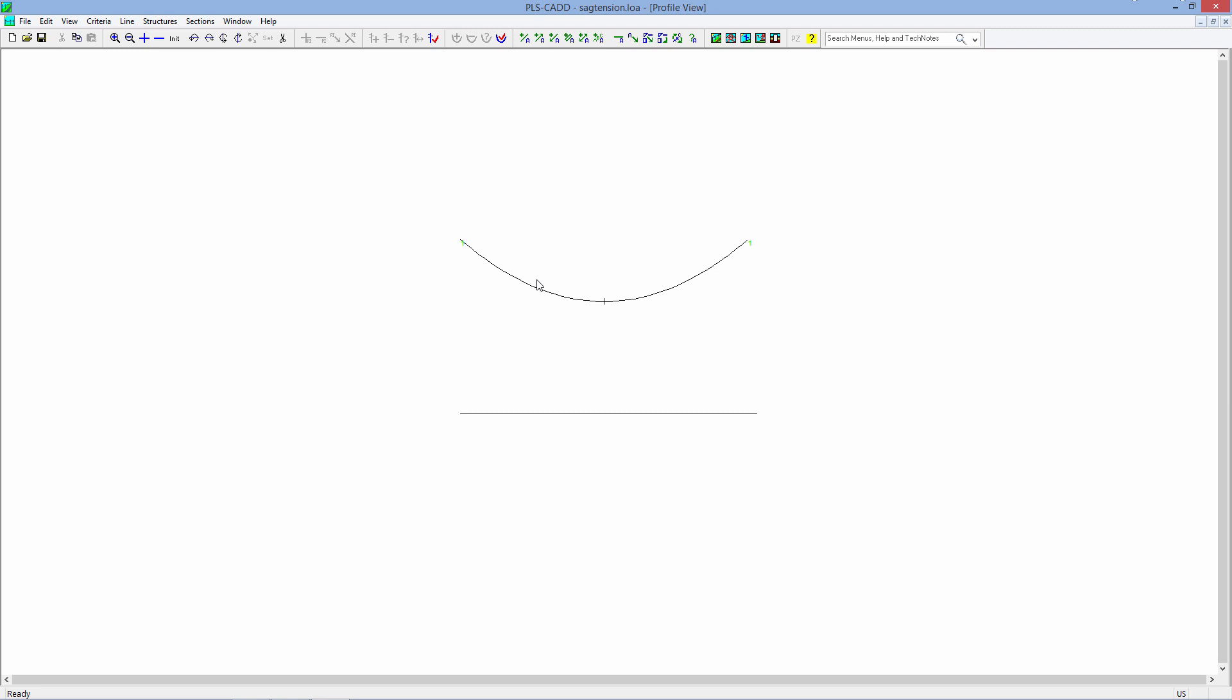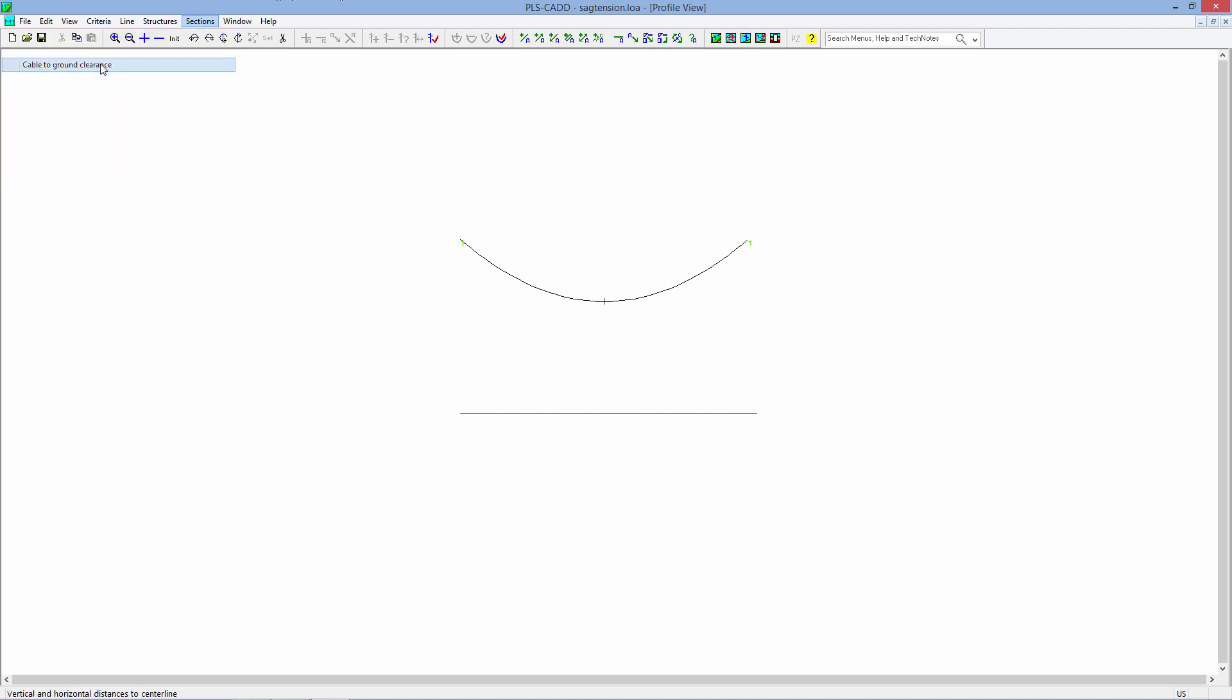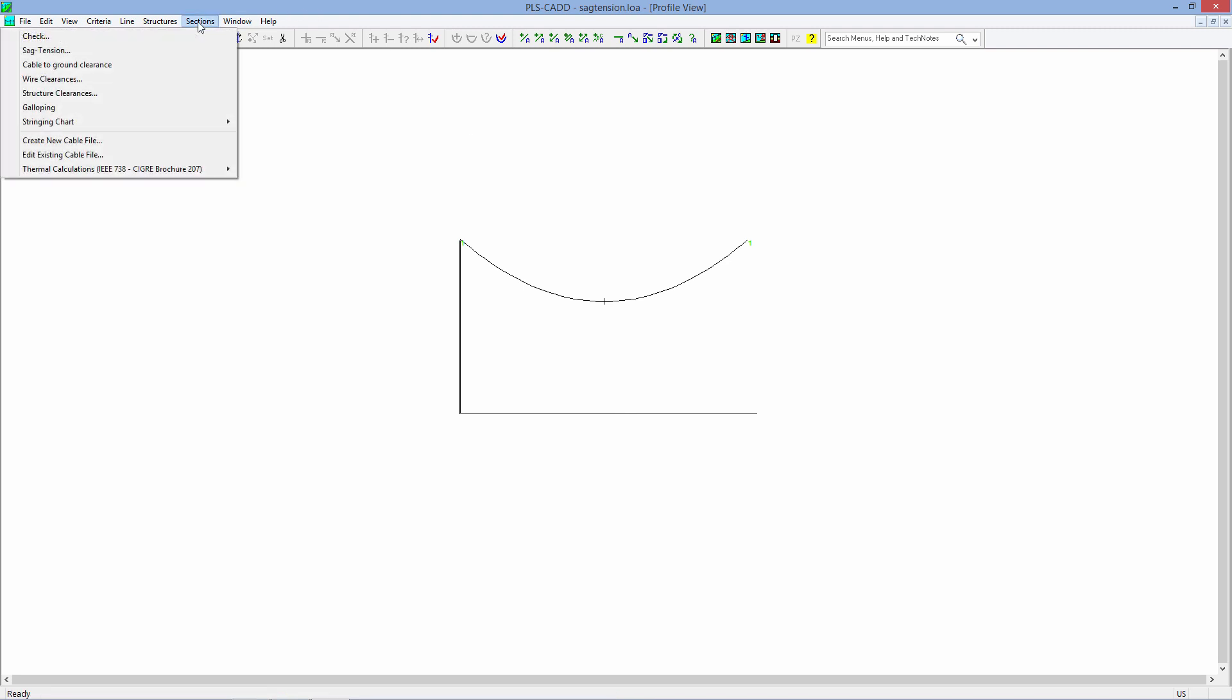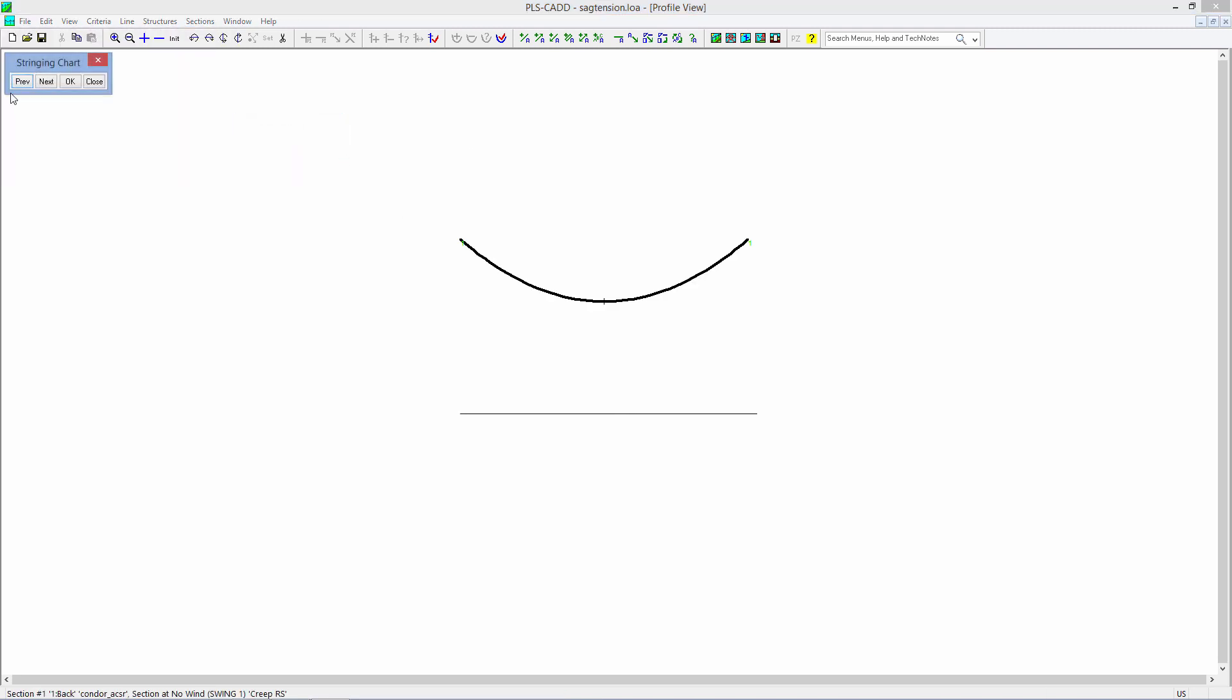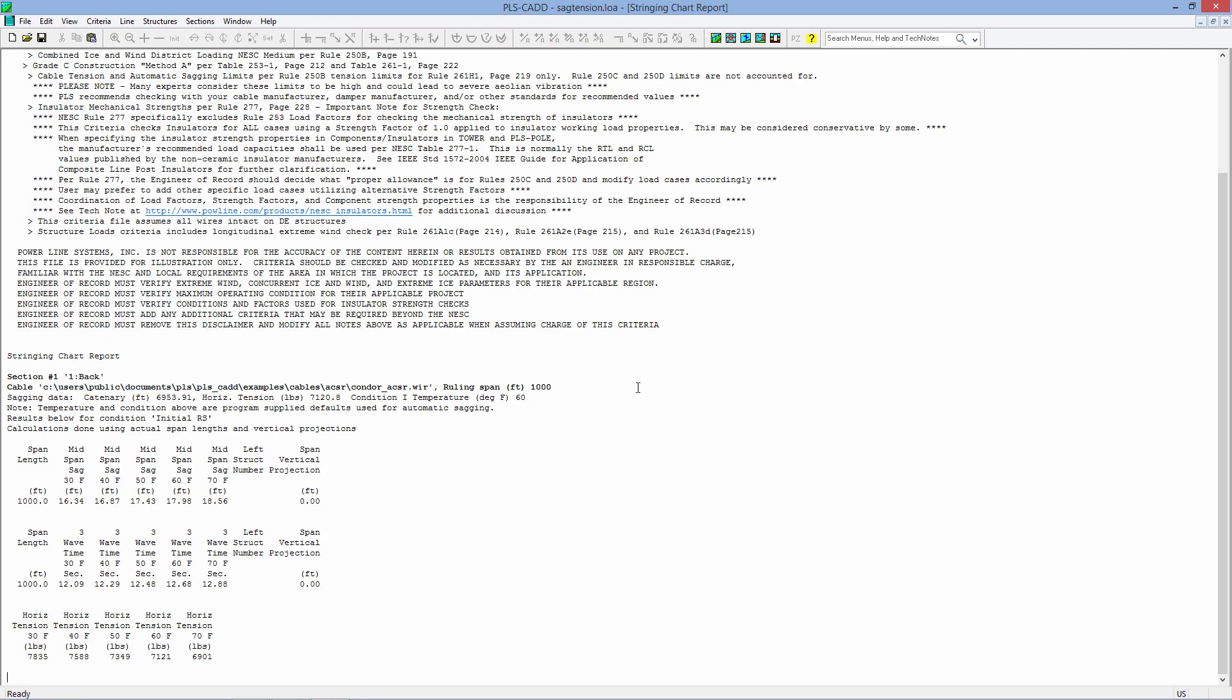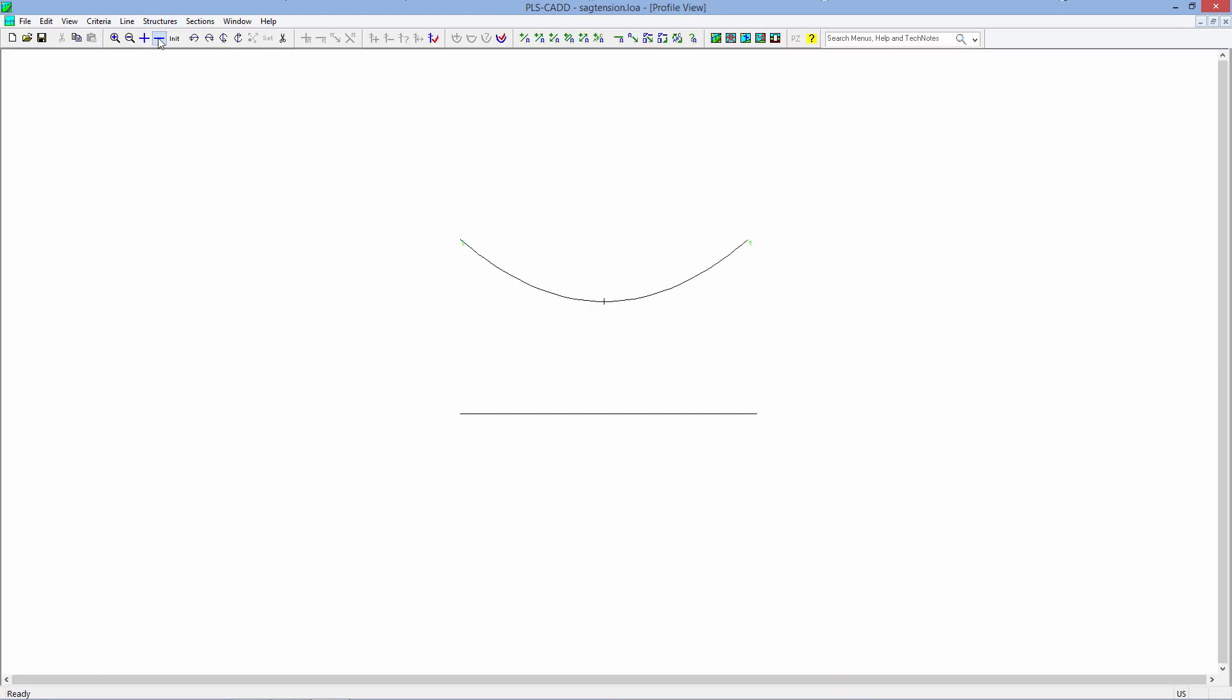So it's very quick and easy just to generate a quick sag tension run report. There's also a lot of other quick functions here. If you want to know how close the cable is going to be to the ground, we can do that function. If you want to come in here and do a stringing chart, so you'd like to get a stringing chart so when they build a line, they would know how to string it. So there's a span length with a mid-span sag at various temperatures, return wave time, and the horizontal tension method if you'd like to use a dynamometer.